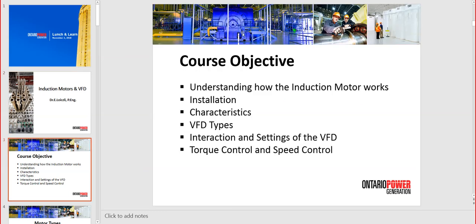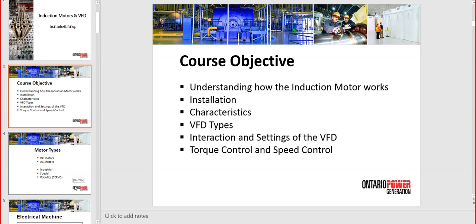The objective of this is to understand how the induction motor works, the installation, characteristics, VFD types, interaction and settings of the VFD, torque control and speed control. Really the VFD can do many things, and depending on the type of VFD you can have a torque control, a speed control, or even a position control. An example where we need position control is on the fuel handling, where we want to have the bridge correctly positioned to actually fill the tubes in the calandria with new fueling. So that's a precise positioning that is done with VFDs.